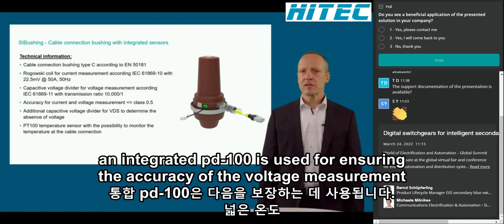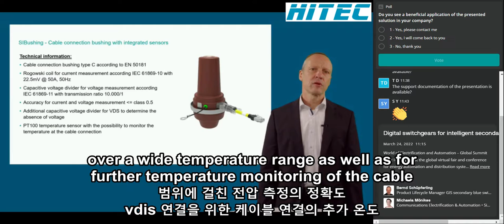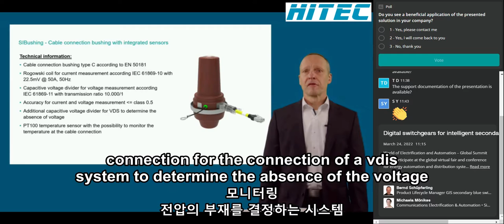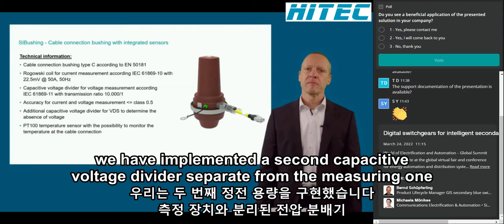An integrated PT100 is used for ensuring the accuracy of the voltage measurement over a wide temperature range, as well as for further temperature monitoring of the cable connection. For the connection of a VDS system to determine the absence of the voltage, we have implemented a second capacitive voltage divider separate from the measuring one. To be able to transfer the sensor information to the control center or into the cloud for further applications, we need further distribution automation devices like FPIs and RTUs.